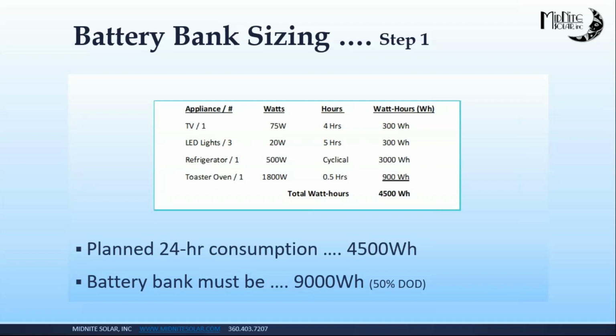You recharge it the next day. Doing that will make those particular batteries last 5 to 6 years on average, or maybe longer if you take really good care of them. So when you design a system, if you're going to go with flooded, sealed batteries, we're going to plan on a 50% depth of discharge. So that means we need to double our bank. If we need 4,500 watt hours, as we did from our load analysis, I'm just going to double that. So my battery bank must be sized to hold 9,000 watt hours of energy.